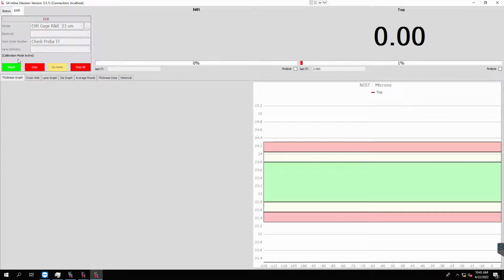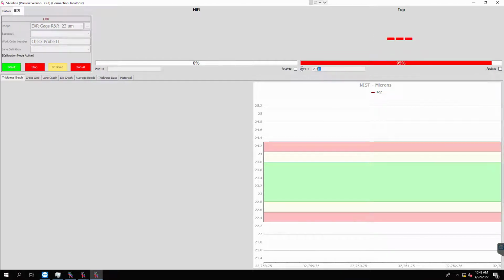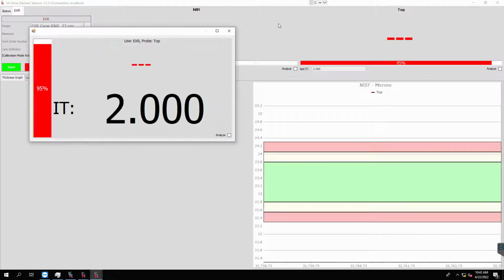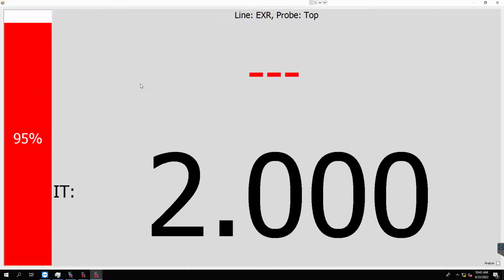For this procedure, there should be nothing underneath the probe. The path should be clear for at least 12 inches, about 300 millimeters. This is also worth checking to make sure the probe is not pointed directly at another light source or an outside window where the sun could impact reflectance. Open a dedicated probe reflectance window by clicking the probe name to allow making adjustments easier to see from a distance. In some cases, you may need to use TeamViewer to remote into the system if the screen cannot be visible to you. Maximize the probe reflectance window to make it easier to see.